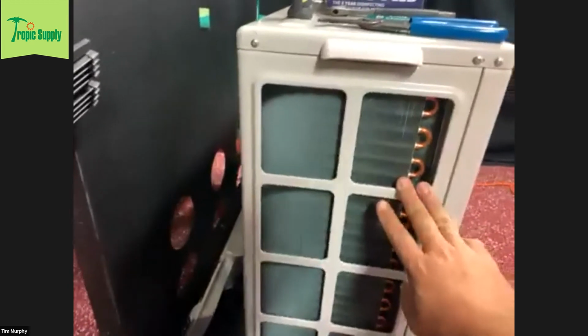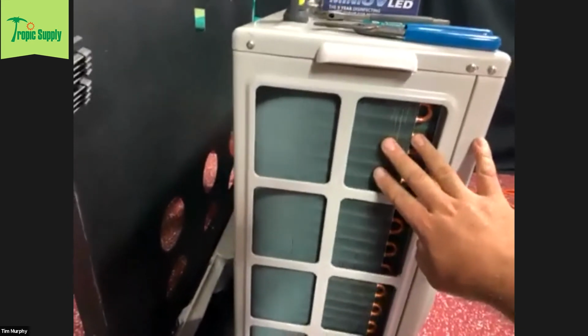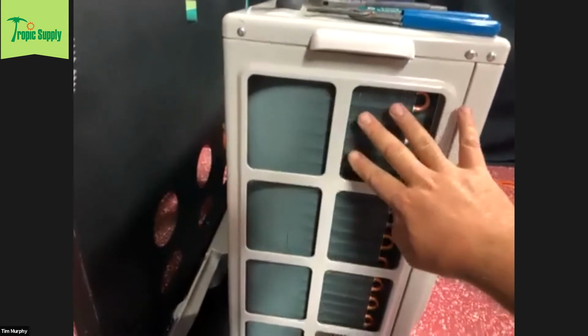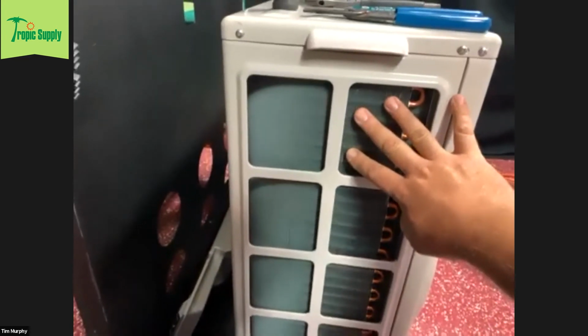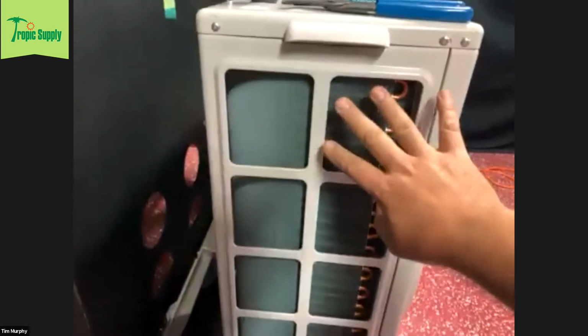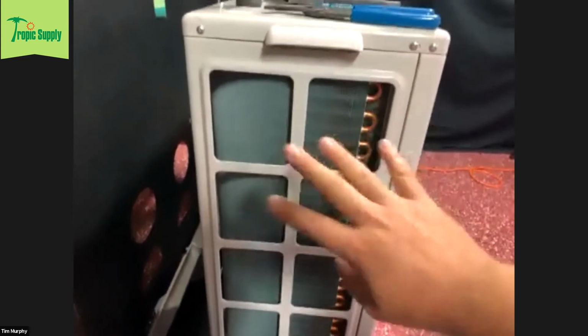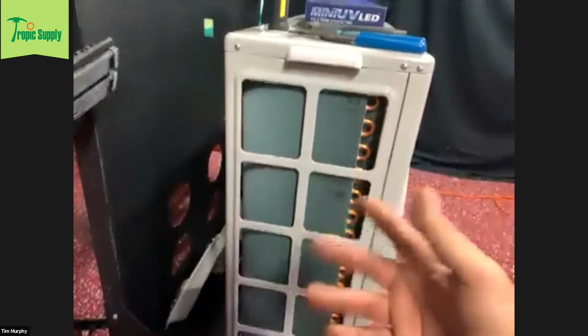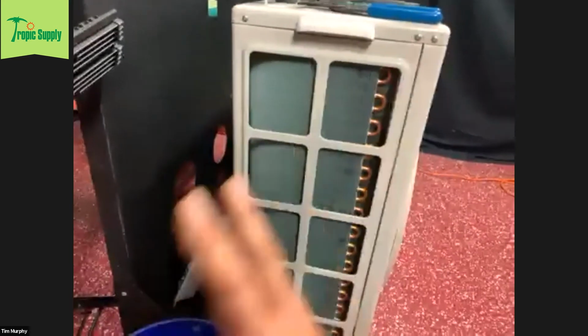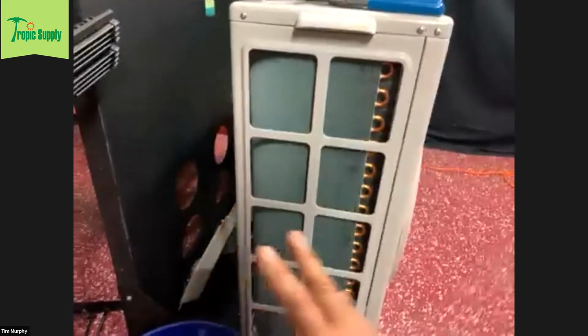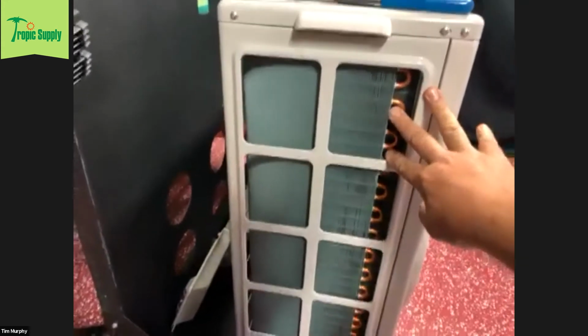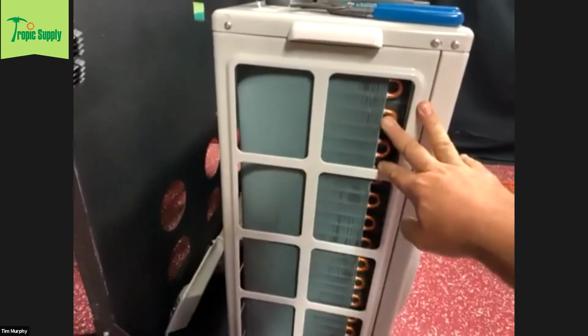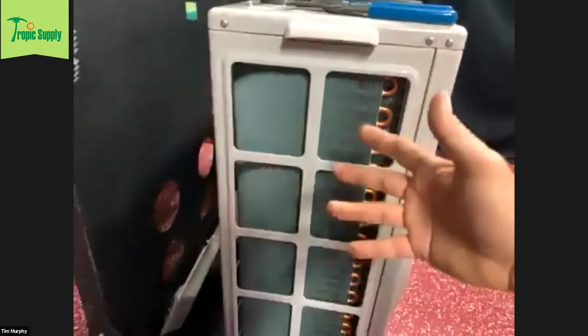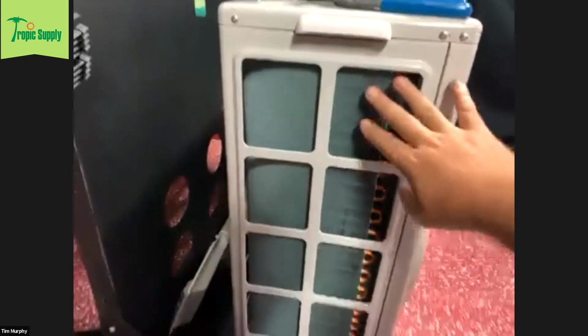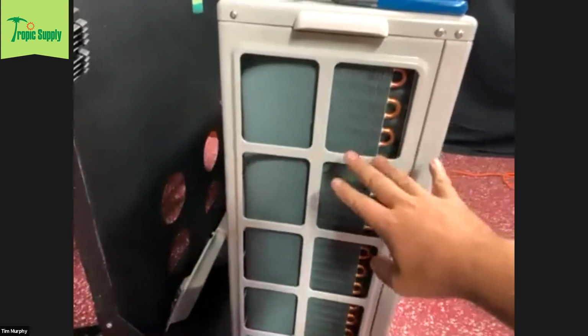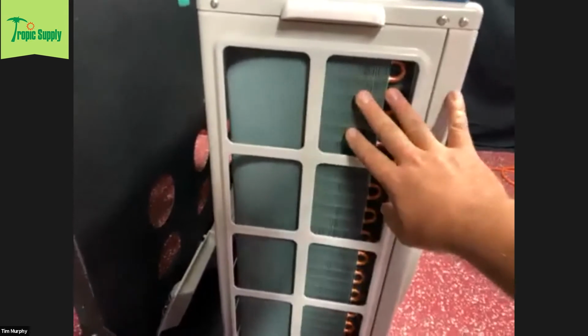While I'm looking at this condenser coil, I do want to mention that Samsung has provided us with a corrosion resistance coating on these systems. All their coils have been coated, and they've actually been tested. A lot of other systems will say they're coated, but there's been no testing on it. Not to say their coating isn't valid, but at least with the Samsung system, if you have a customer closer to the beach who has questions, you can offer them this: the Samsung system has passed a 480-hour salt spray test on their coils, so it's rated to be near the beach.